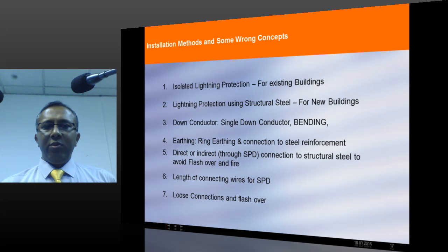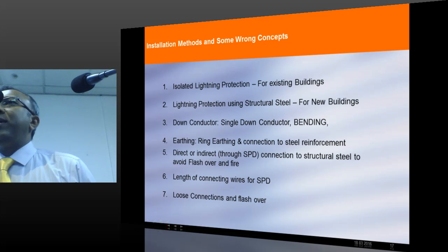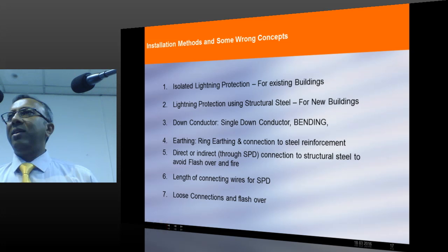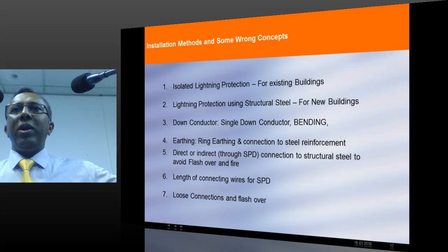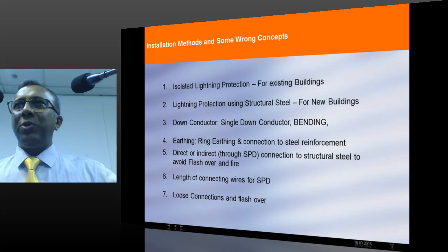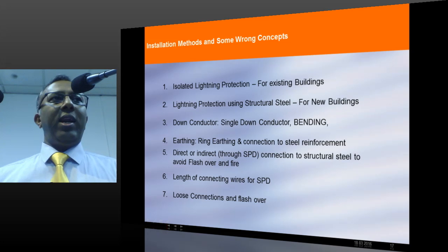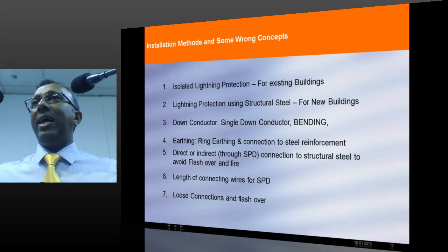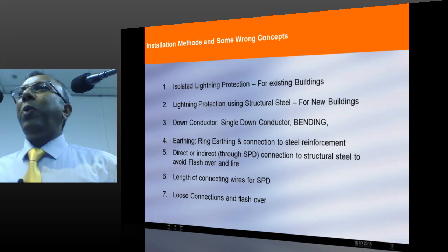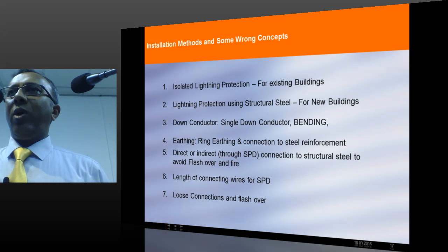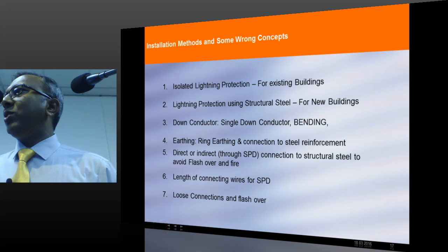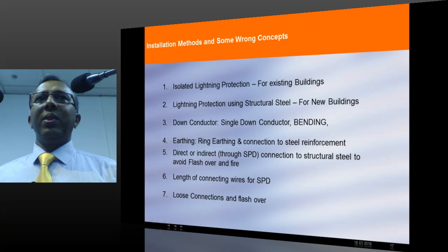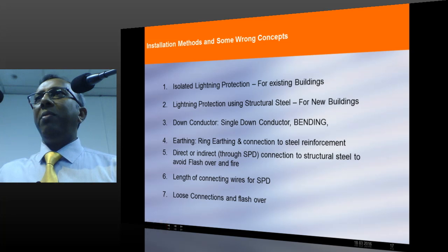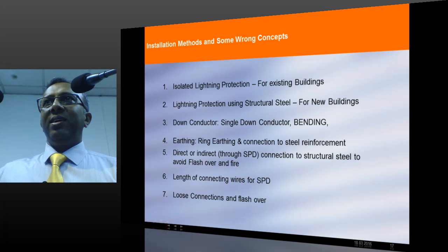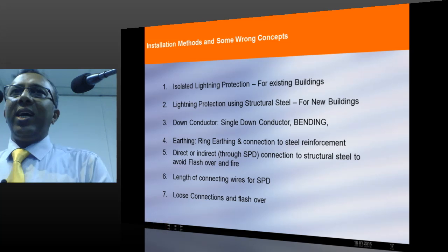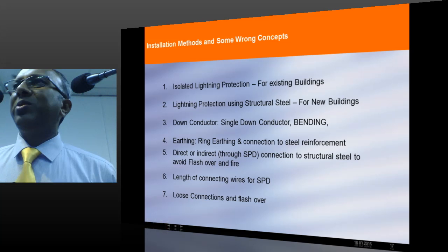Now you know, whenever we go for an assessment of an installation, the problem which we face is a single down conductor, which is quite common in several parts of, especially, India. In several buildings, one down conductor, sometimes two down conductors for a large building. If we explain that, look, you are making a mistake, two down conductors will not do, maybe you need 5 or 10, but then the first argument comes: no, my architect will not allow. My architect doesn't want to show a down conductor outside the building because it does not look nice.